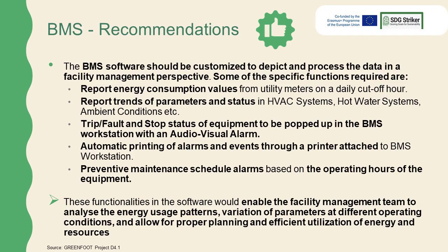Additionally, the BMS software should be customized to depict and process the data in a facility management perspective. Some of the specific functions required are: report energy consumption values from utility meters on a daily cutoff hour, report trends of parameters and status in HVAC systems, hot water systems, ambient conditions, etc. Trip, fault, and stop status of equipment to be popped up in the BMS workstation with an audio-visual alarm. Automatic printing of alarms and events through a printer attached to BMS workstation. Preventive maintenance schedule alarms based on the operating hours of the equipment.